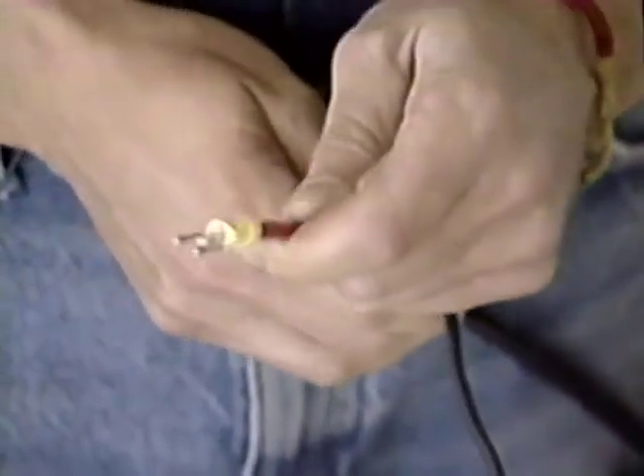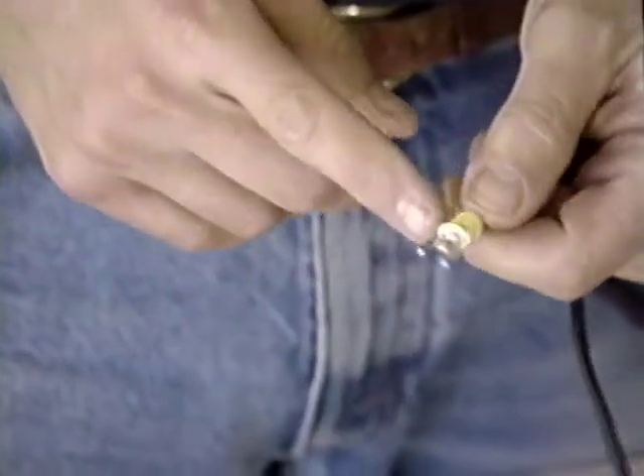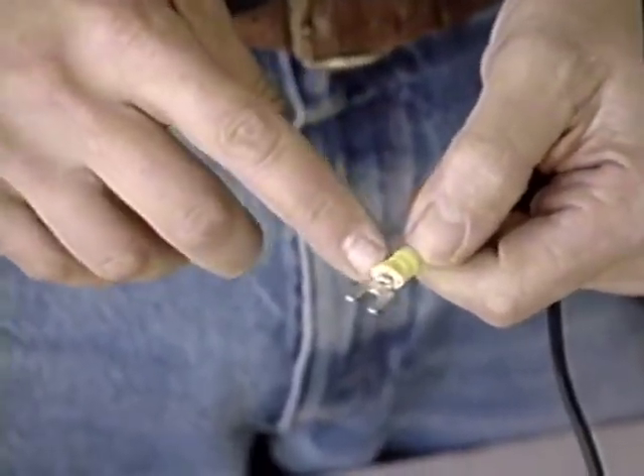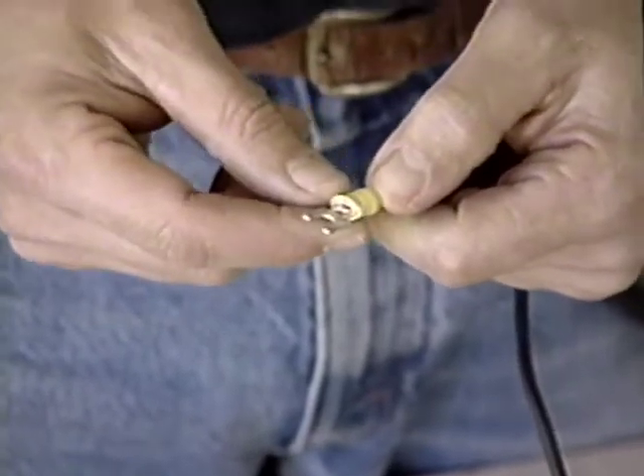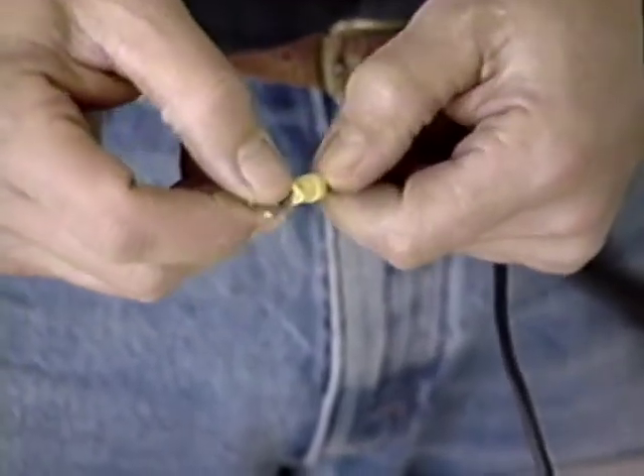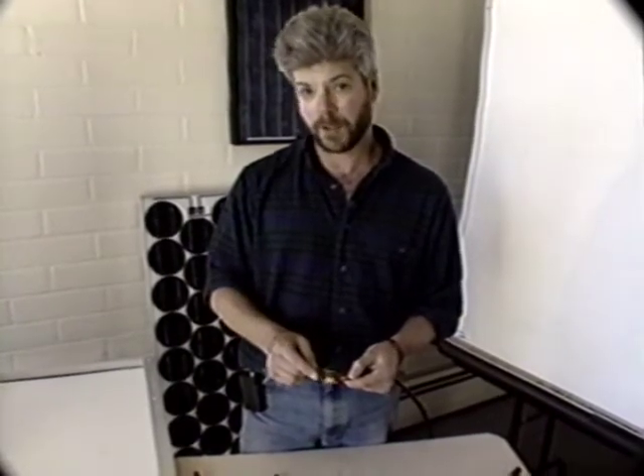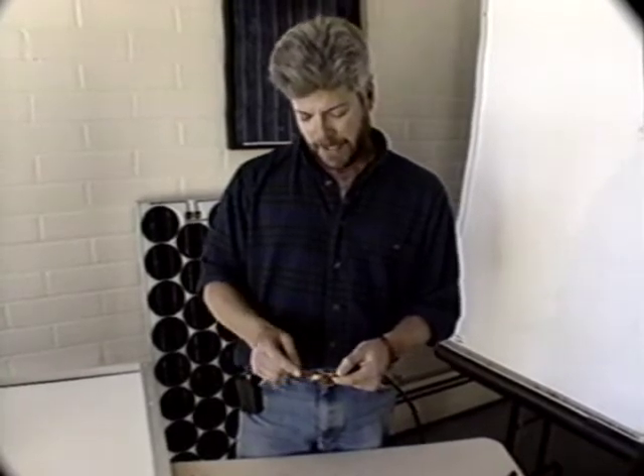One way to improve this connection would be to remove this little insulated piece and solder this connector to the wire as well. Soldering takes some time, but it's worth it when we're looking for a 20-year connection that's going to be hard to get to and maintain. A soldered connection means there's going to be less resistance, more surface area, more contact for the electrons to flow. It doesn't help structurally — we still need a mechanical crimp connection — but the solder adds more surface area.